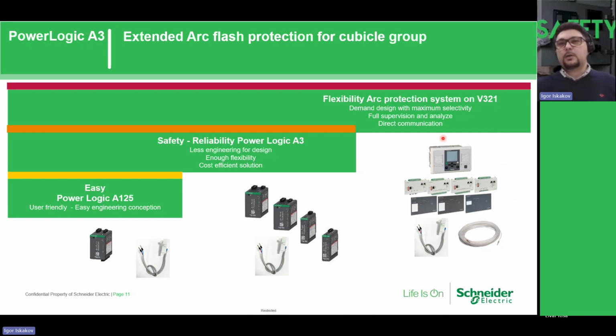And of course, if we go to a more high-end application, it will be the V321 solution of the Schneider Electric arc flash protection, where we have a main unit, a slave unit, and sensors. The main unit has logic and events behind it, and can communicate directly to the SCADA. So this is very high level, and in case the customer is interested in having all possible information about the arc flash protection, it will be possible using the V321. But today we speak more about A3.